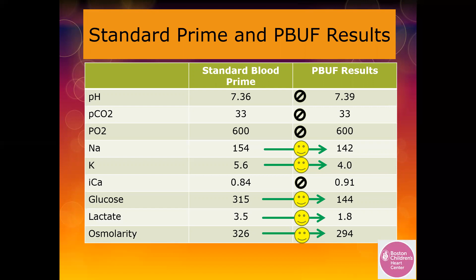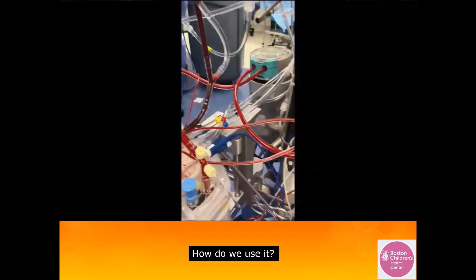Transitioning to ultrafiltration during bypass, this quick video shows active conventional ultrafiltration with the same blood flow path as that which was used for PBUF. Again, this technique is very simple and easy. Active ultrafiltration can be performed at any time during bypass. The flow path is the same as that which was used during pre-bypass ultrafiltration, running from the venous line to the ultrafilter head, to the top of the hemoconcentrator, to the bottom, and then back to the venous reservoir.